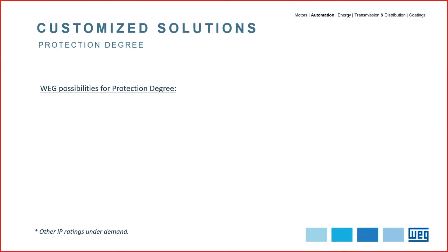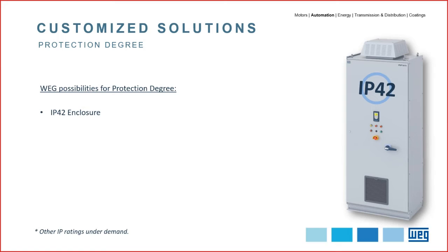And now let's go through the most common possibilities of protection degree supplied by WEG. The IP42 enclosure is the standard enclosure offered by WEG. The standard product line mentioned in the beginning of this presentation comes with IP42 protection degree enclosures. This protection degree offers protection against access to hazardous parts with a wire and against vertically falling water drops when the enclosure is tilted up to 15 degrees.